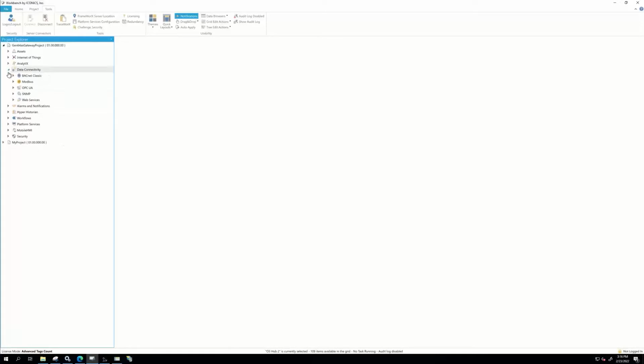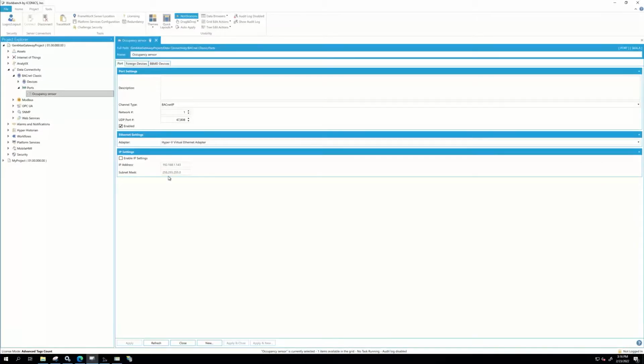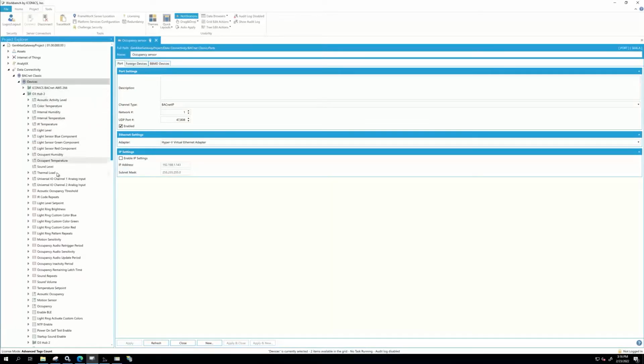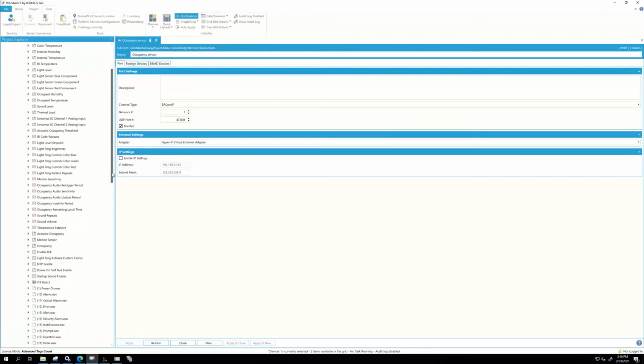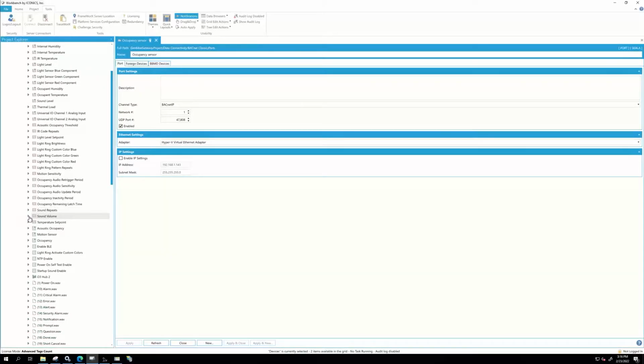For data connectivity to talk to devices, you look at the data connectivity module, and depending on what protocols you've installed, I've installed BACnet and told it that I have an occupancy sensor running on my local network. If I do a network scan for devices, network discovery, it would discover everything on there. In this case, it discovered the occupancy sensor, and on it, a huge number of objects that sensor is publishing or responding to queries on.